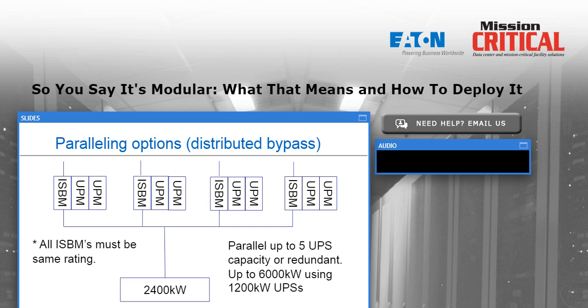That's a good question, and it's a little difficult to do because when we do redundant UPMs, we're by definition tying them together at a single point. So there is a single point of potential problem there if I were to have a fire in a tie cabinet, just to give you a doomsday scenario there. Even a multi-module parallel system would not be able to provide a protective path in that case. That's why we see the large number of dual bus architecture systems out there.